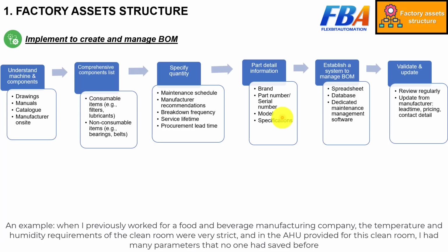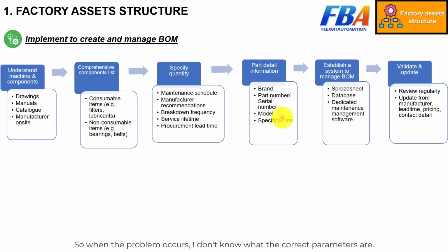For example, when I previously worked for a food and beverage manufacturing company, the temperature and humidity required of the clean room were very strict. And in the AHU provided for this clean room, I had many parameters that no one had saved before. So when a problem occurs, I don't know what the correct parameter is.